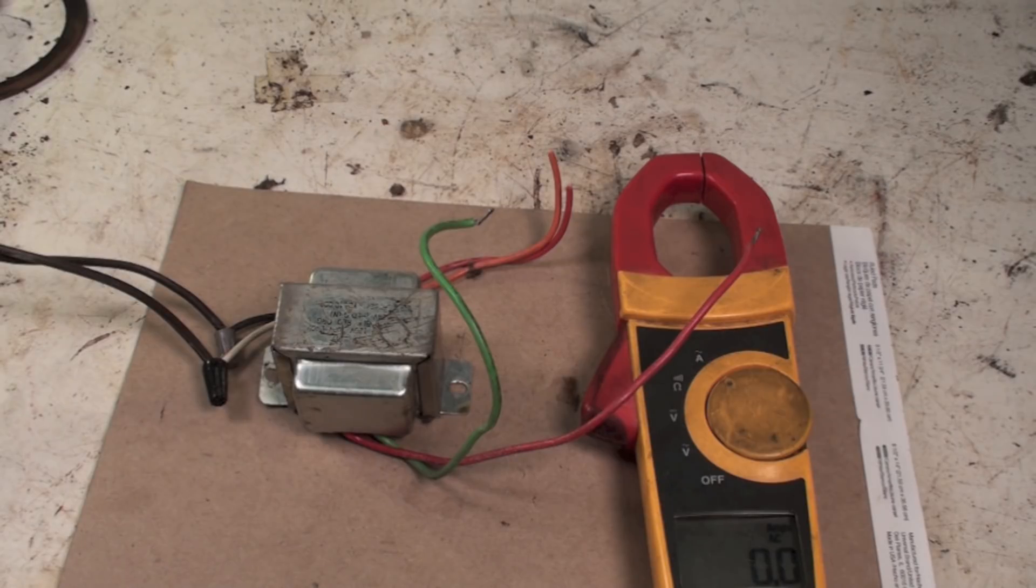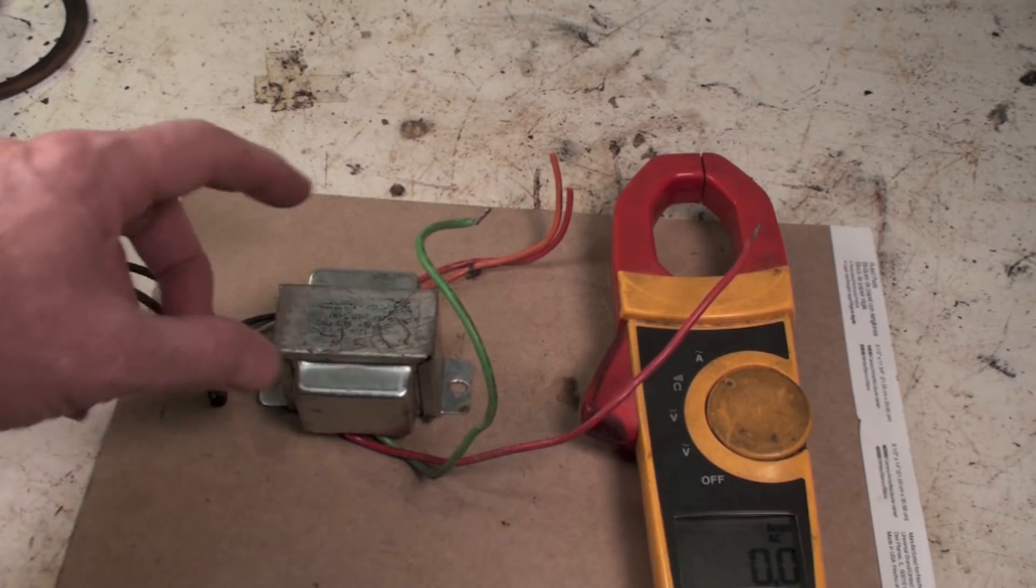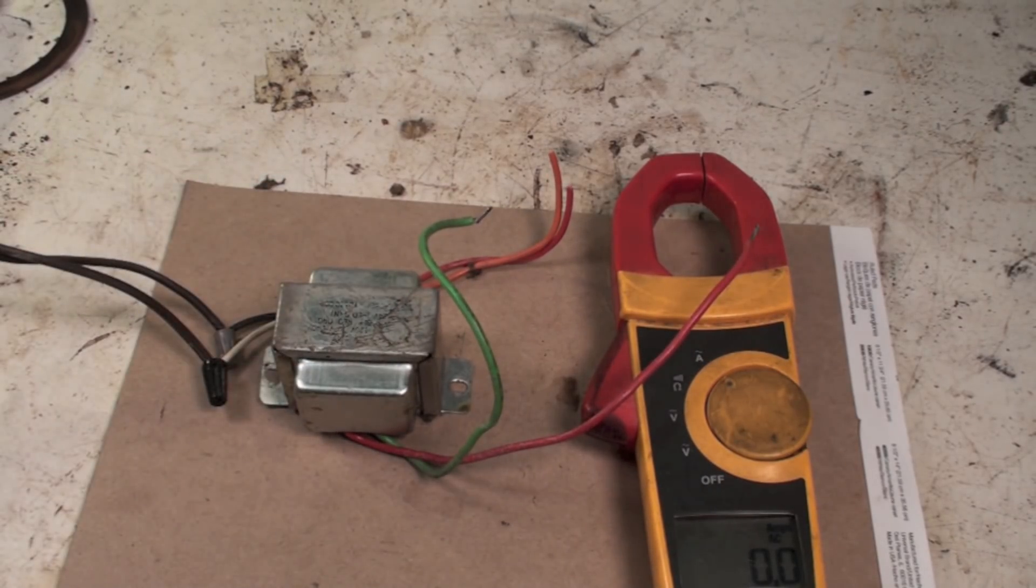So if you have a transformer that has failed and you replace the transformer, when you put the new one in and it fails immediately, these things fail two ways. One, if there's an internal fuse, they'll just fail immediately just like that. I don't actually recommend using a transformer with a fuse in it.